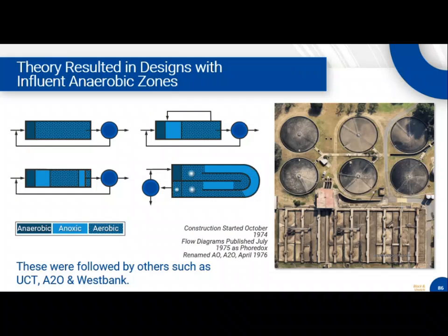So you're trying to get your PAOs to get their fill of brats. And then you have the brats that are left over, and maybe like a side salad, that's available in the anoxic zone. Right? And that's what you denitrify with, the leftovers and the stuff that you don't want to eat as much as the brat. And then you get your aerobic conditions for nitrification. So if there's plenty of brats, we can be very simple because there's plenty to go around. As we start to get limited, we need to have some anoxic conditions downstream of the anaerobic zone, and we do the denitrification with the leftover BOD. We're still prioritizing BOD for our PAOs.